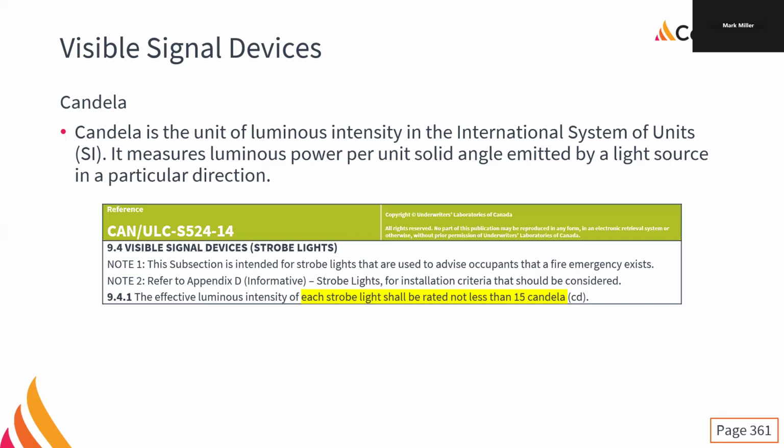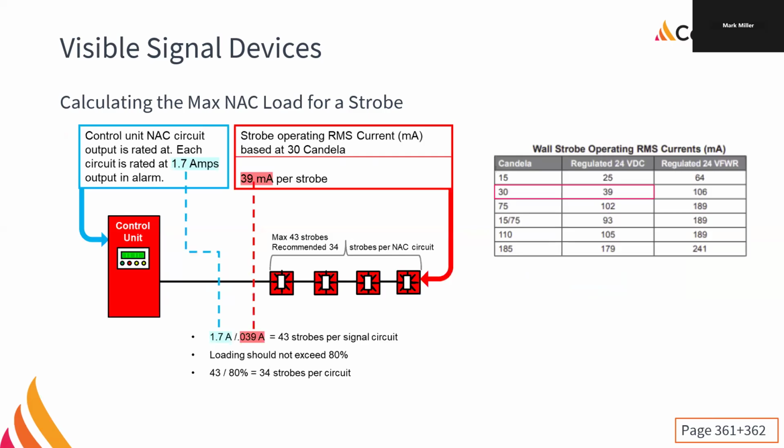But you can get pretty bright. The minimum candela rating for smoke detectors being used as smoke alarms in sleeping rooms is 175 candela, I believe. Like it is aggressively bright. You can see them with your eyes closed. It's absolutely crazy. This is pretty generous, this one here.